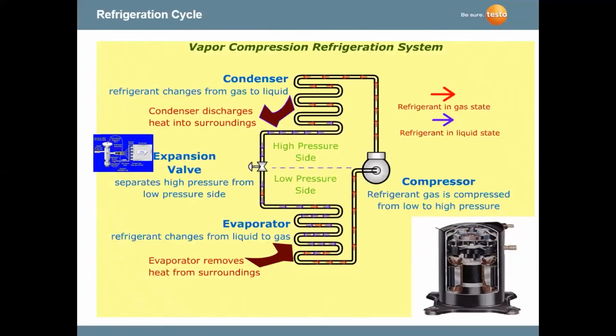But if we start at the compressor, the refrigerant vapor is compressed in the compressor and now moves to the condenser. The refrigerant is at a high temperature, high pressure vapor. Since there is more heat in the refrigerant and less heat in the outside air going through the condensing unit, the condenser coils are transferring the heat from the refrigerant to the outside. And as this refrigerant rejects the heat in the condenser, the refrigerant condenses and becomes a liquid. So you're going from a vapor to a liquid. At the condenser outlet, the refrigerant is now a high pressure liquid.